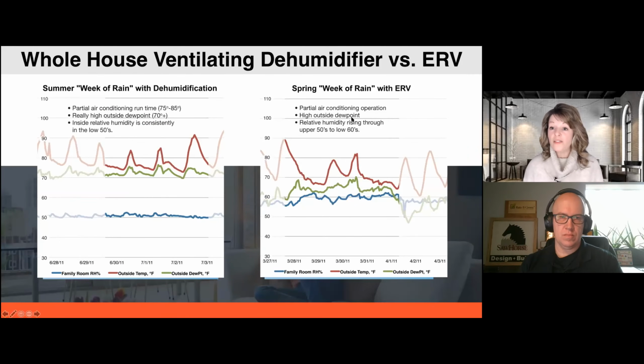So this is a house down in Orlando, Florida. It was an NAHB Emerald Greenhouse certified, and the homeowners had an ERV in the house, and we're showing partial air conditioning operation here, because we're not running at peak loads where the air conditioner might be able to handle that moisture a little bit more. But here, this blue line is the RH inside, and the green line is the dew point outside. And our RH here is 60% on this line. And you can see it's consistently over that, the relative humidity in the house, and it's following the dew point outside. And these homeowners were very uncomfortable in their homes.